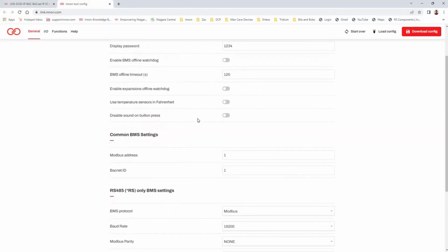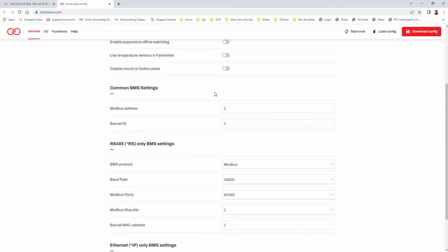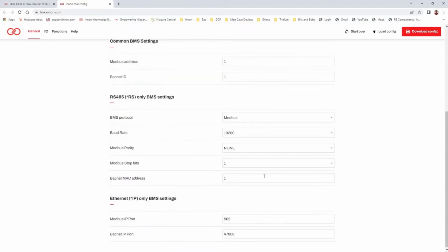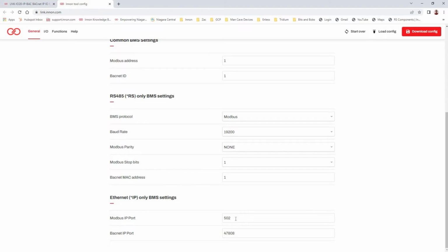Just to note about settings that don't apply - say you've bought an IP module, and the IP modules do Modbus and BACnet. You've got a lot of RS485 settings here which don't apply - you don't have to worry about deleting them, just ignore them, they won't get loaded in or mess things up. If you had an Ethernet version, you just want to set the ports up down here on this page.